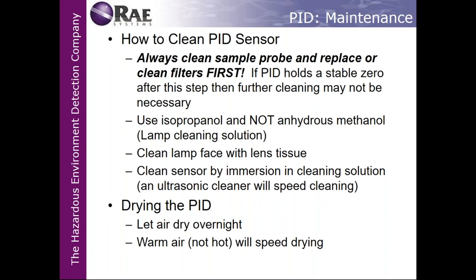But you can use isopropanol alcohol and not anhydrous methanol alcohol to clean the lamp itself. You just basically would get a tumbler or a drinking glass. You would fill it up with the solution, take the sensor out, submerge it, and shake it around for about 10, 15 seconds. Do not use air or compressed air to shoot at it. So it's important for you to understand, let it air dry overnight, come back next morning, reassemble it, calibrate the instrument, you should be good to go.